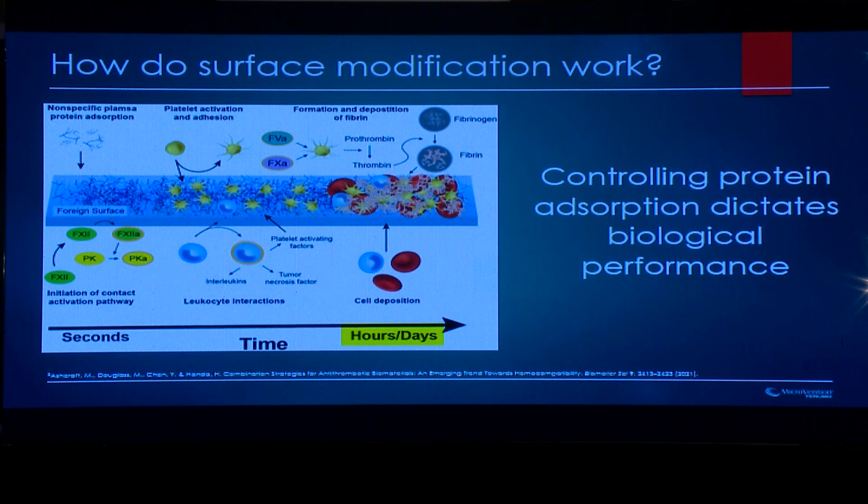It's been known for some time that PMEA, the poly-2-methoxyethyl acrylate, has highly hemocompatible properties that were not shown by other polymers. More recently, the mechanisms for foreign body thrombus formation have been understood. The key to the hemocompatibility of PMEA is its controlled hydrophilicity, which is the effect that this has on the boundary water layer, and then the secondary effect that this has on protein adsorption and then subsequently platelet aggregation.